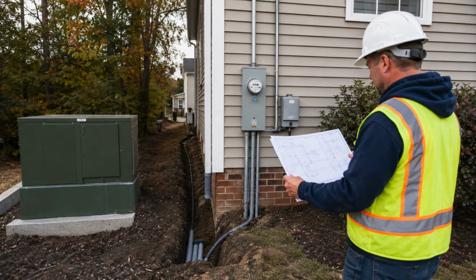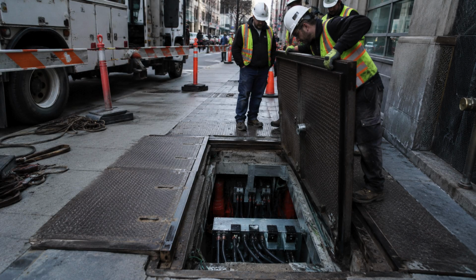Water intrusion can damage underground cables and connectors. Flooding can affect the vaults and pad-mounted equipment. Soil movement can stress cables. Dig-ins from construction crews can damage underground infrastructure. Older underground cables can deteriorate over time. And if underground systems are not mapped and maintained carefully, repairs and future construction become more difficult. This is especially important in cities where the underground space is already crowded. Below the street, there may be electric cables, gas mains, water lines, sewer lines, fiber optic cables, steam systems, drainage infrastructure, and abandoned facilities from older utility work. Installing new underground electric infrastructure in that environment can be extremely complex. It is not just a technical decision, it is a coordination problem. Every underground project has to respect what is already in the ground.